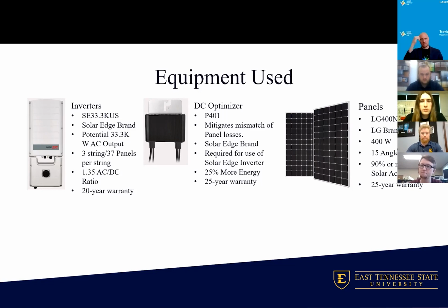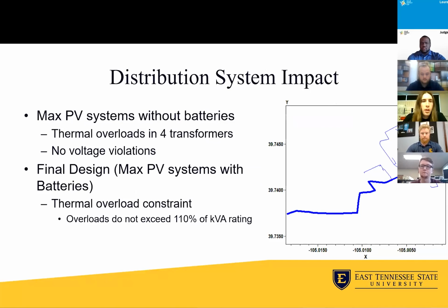The team modeled PV systems in OpenDSS to analyze the design's impact on the distribution system. According to our analysis, without batteries the maximum feasible PV systems do not produce any voltage violations in the distribution system. However, the simulation detected 4 transformers with significant overloading.